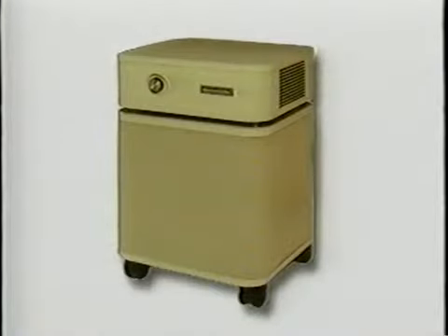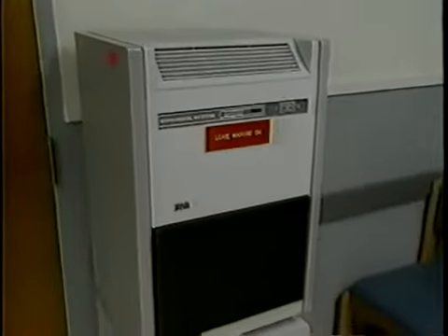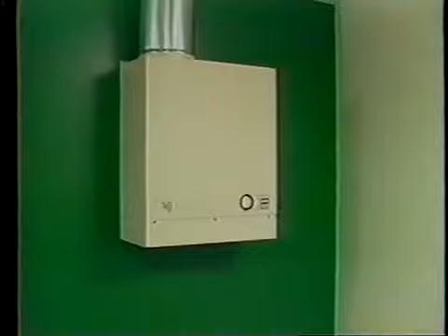These units come in a number of different configurations. The most common are small portable units that can produce 100 to 400 CFM. The larger portable units are rated for 150 to 800 CFM. Other designs include ceiling-mounted and wall-mounted units. The actual amount of air produced by these units is difficult to measure compared to a ceiling or wall outlet, because you can't just put a flow hood up against them. Also, they may produce less air than the nameplate lists.